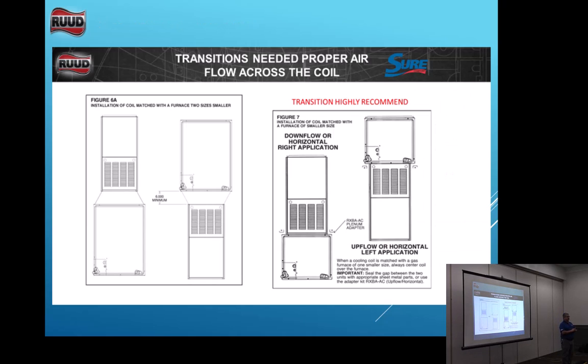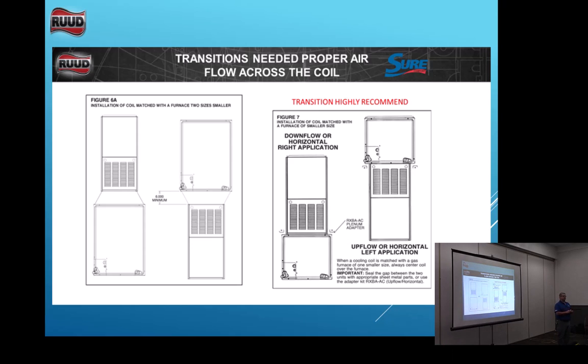Okay? Let's talk about this in airflow. Okay, a little bit. So, in the installation instructions for furnaces and coils, if you have a 17-inch furnace and you have a 17-inch coil, it says in the installation instructions, it is recommended to use a transition but not required. If you have a 17-inch furnace and a 21-inch coil, it says it's recommended to have a transition but not required. If you have a 17-inch furnace and a 24-inch coil, it's required to have a transition. Okay? But you wouldn't see that very much probably, but that's what it is. It's in there.